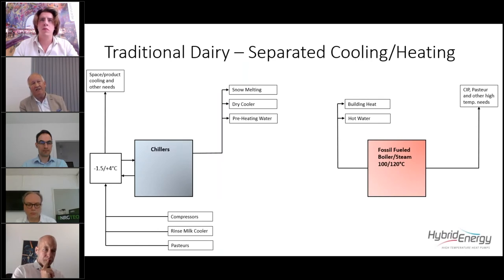Going a little bit into the technical side, this sketch shows a traditional dairy where you have separate cooling and heating arrangements. On the chiller side, you have the pasteurizer, rinse milk, and compressors adding in energy. Then you have preheating of water, dry coolers when needed with excessive heat, and snow melting. And of course, for the process support, you have a supply. On the warm side, you have the fossil fuel steam boiler, up to 120 degrees Celsius. It supplies hot water and building heat, and of course what is required for the operation of the dairy: CIP, pasteurizer, and other high temperature needs.